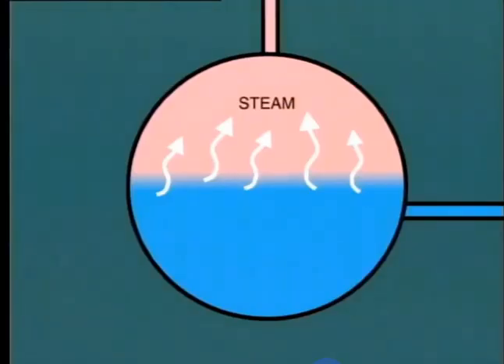Let's take a closer look at each of these items. First, the problem of scale. As much as we try to provide perfectly pure water to the boiler, it is inevitable that some small quantity of contaminants get through and concentrate in the boiler water as more and more steam is evaporated. As water evaporates into steam, the solids contained in the water remain behind, and this concentration increases as more and more steam evaporates — this is the situation which occurs in the boiler.